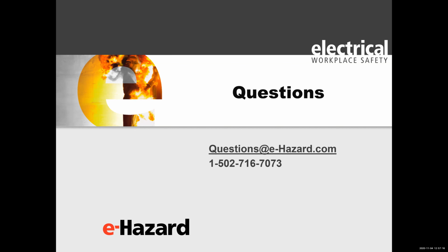Thank you, Hugh. Next question we have for you is, has anything changed in terms of open air battery racks as compared to battery cabinets where an arc flash comes directly out at a person? Yeah, I don't think there's any big changes there, because I think when we went back and looked at the DC section, and I was on the DC task force, I think we found we were probably on average slightly over predicting. Did we make any changes to batteries, open rack versus closed rack? I don't think we did.